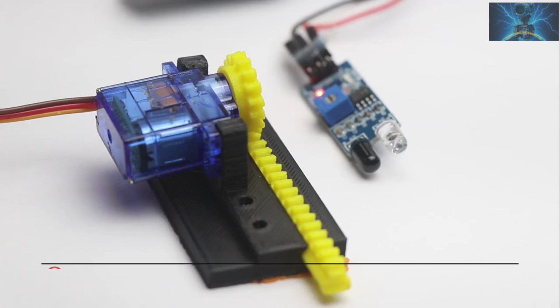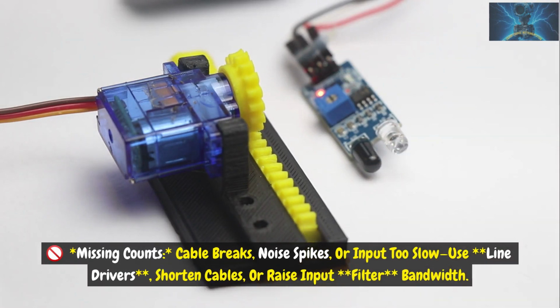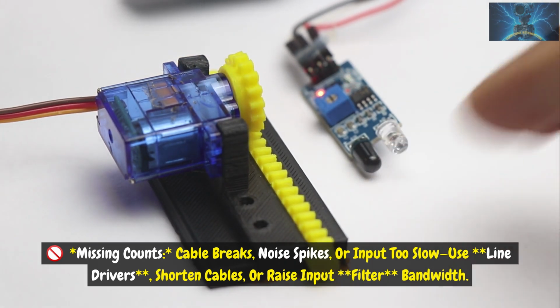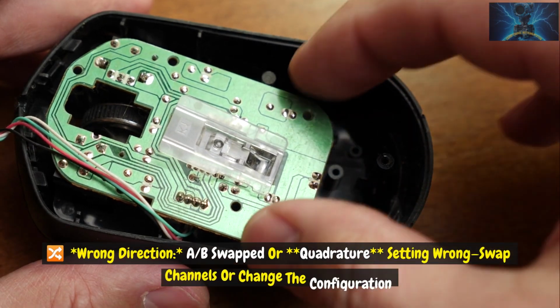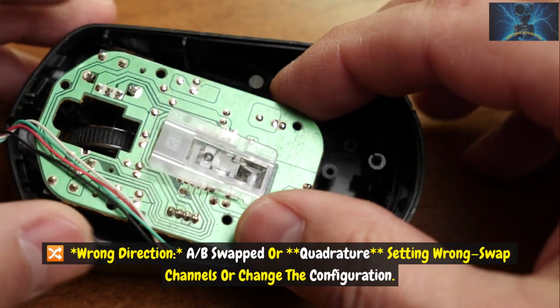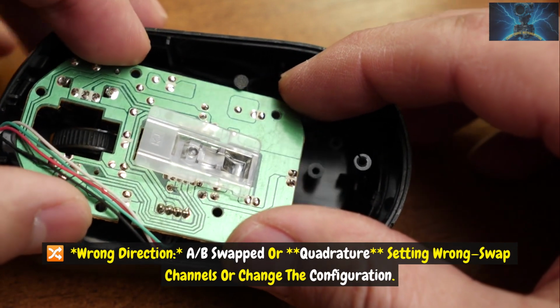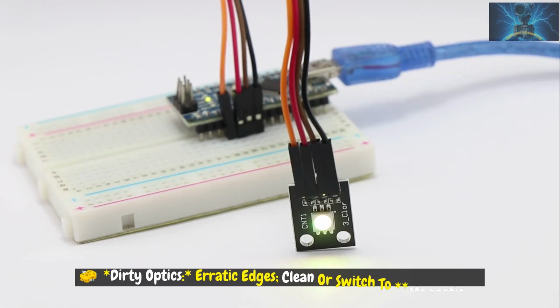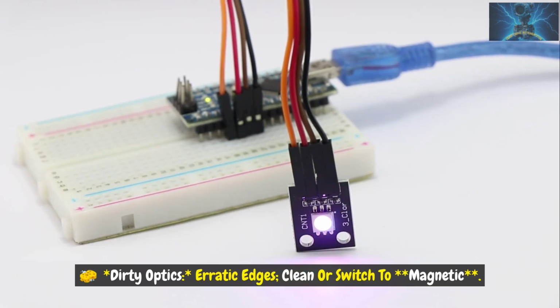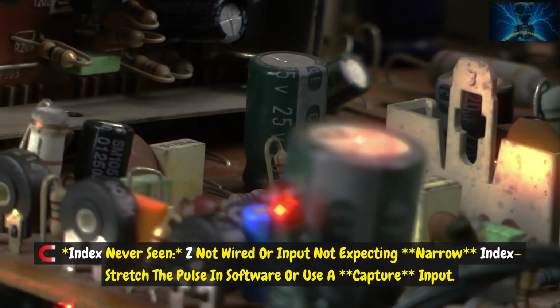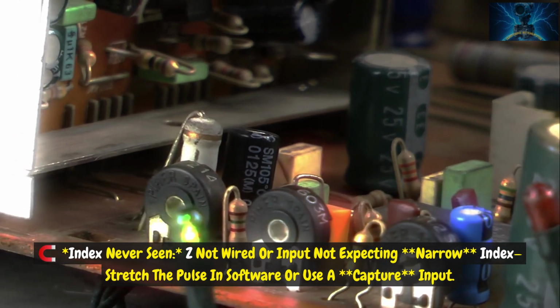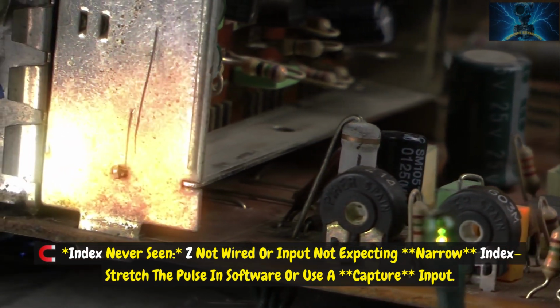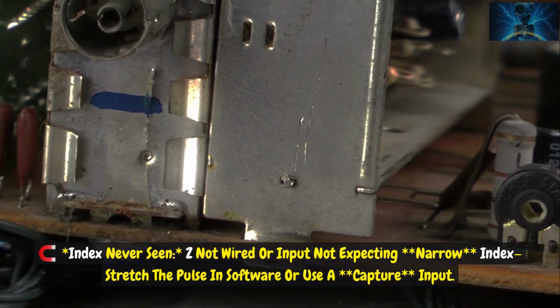Troubleshooting field realities. Missing counts, cable breaks, noise spikes, or input too slow: use line drivers, shorten cables, or raise input or filter bandwidth. Wrong direction: A and B swapped or quadrature setting wrong. Swap channels or change the configuration. Dirty optics and erratic edges: clean, or switch to magnetic. Index never seen: Z not wired or input not expecting it. Narrow index: stretch the pulse in software or use a capture input.